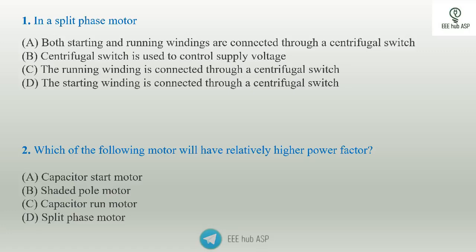First of all, this is the split phase motor. There are two types of windings: starting windings and running windings. The starting winding is in series with a centrifugal switch. At 70% to 80% speed, the centrifugal switch will automatically open, disconnecting the starting winding, and the motor runs on the running winding.